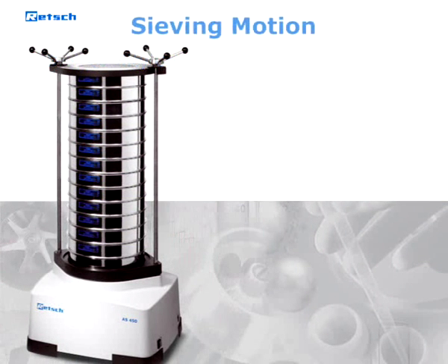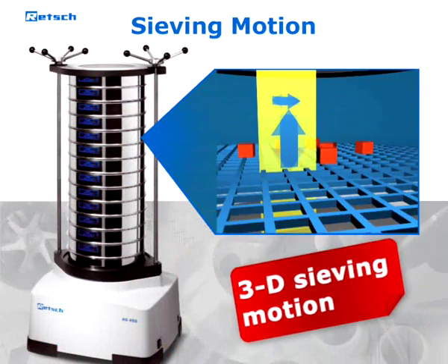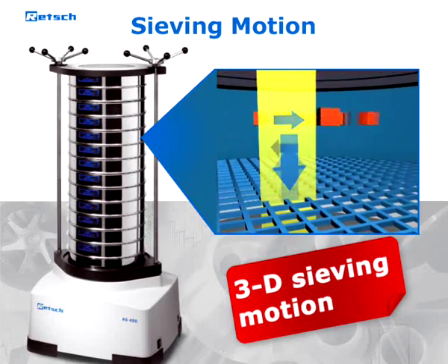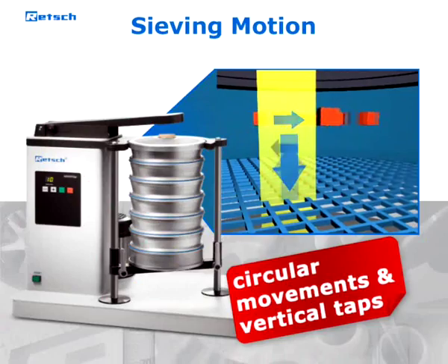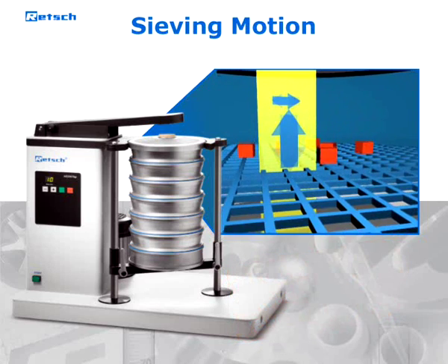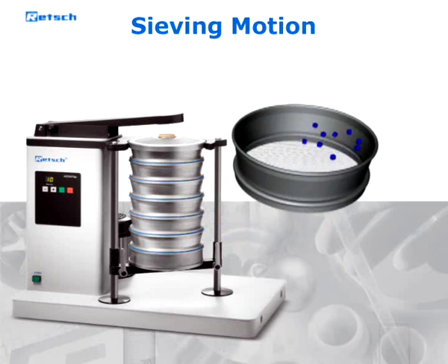Whereas most other Retsch sieve shakers let the sample move over the sieve surface through an electromagnetically induced three-dimensional throwing motion, the AS200 TAP generates this movement via mechanical drive, creating superimposed circular movements and vertical taps. This particular sieving motion is characteristic of TAP sieve shakers.